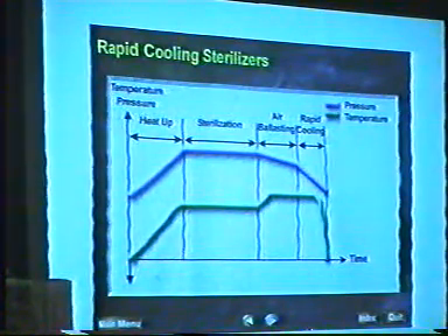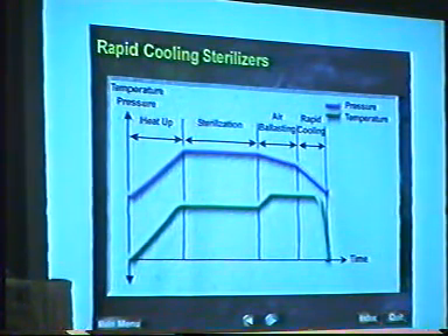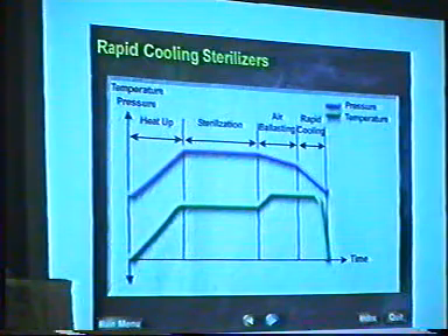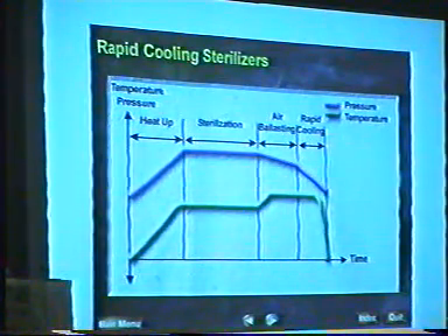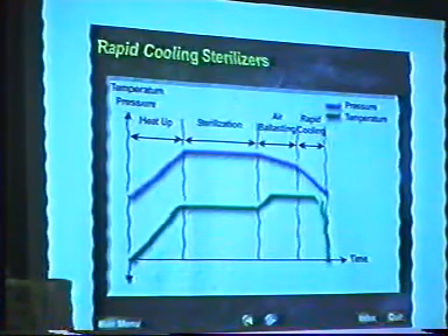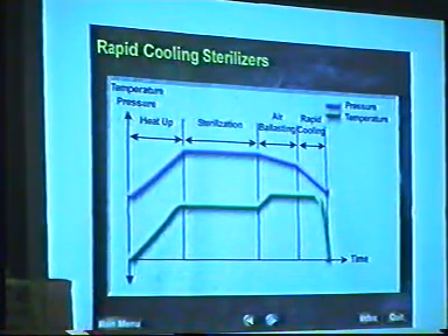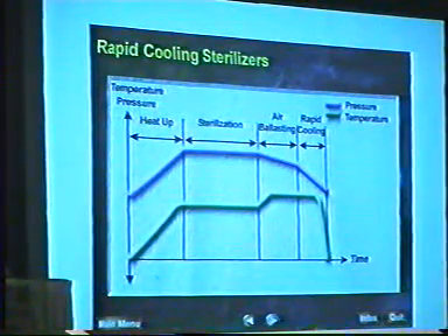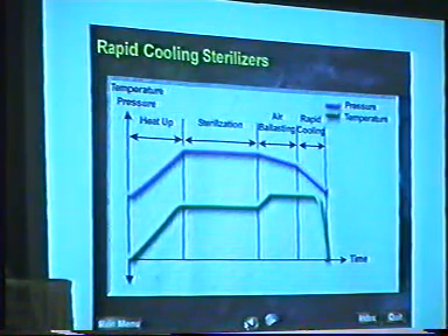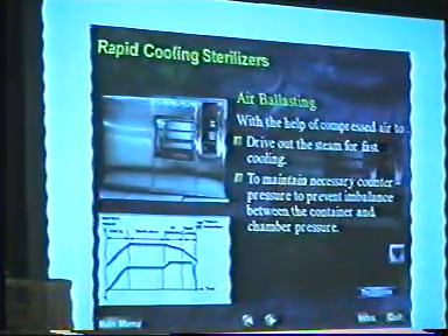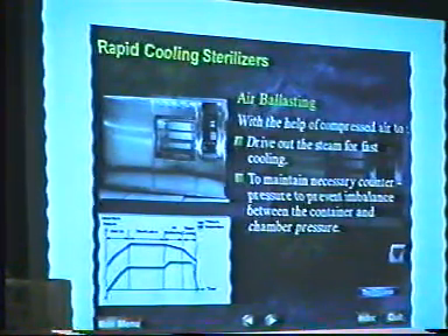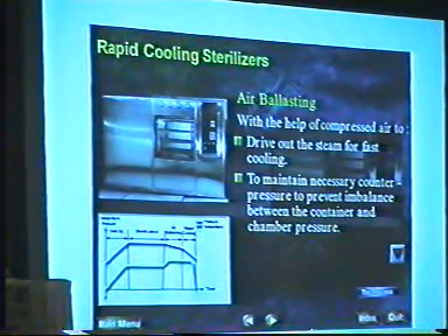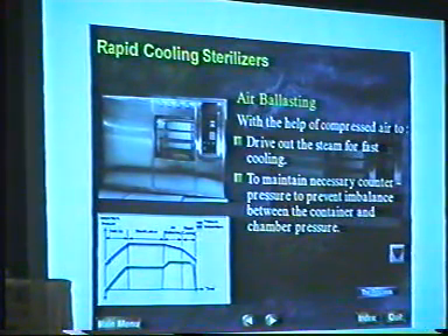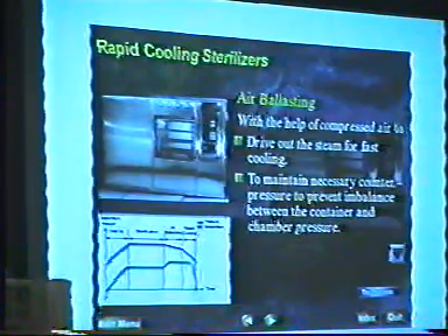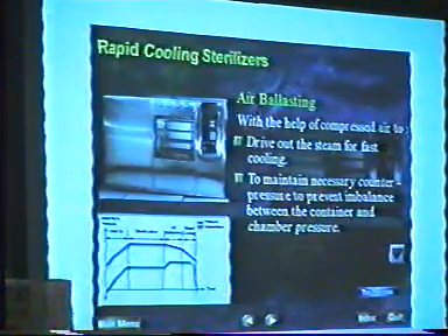Even during sterilization hold, there are some pressure fluctuations where container and chamber pressure can be at opposite ends, and you will find differential applied in a different way. However, the process has served a lot of purpose so far as the LVP industry is concerned. And till the advent of new processes like superheated water spray sterilization or isothermal sterilization, this process was used almost universally for all LVP applications.